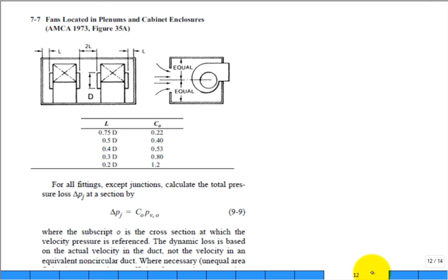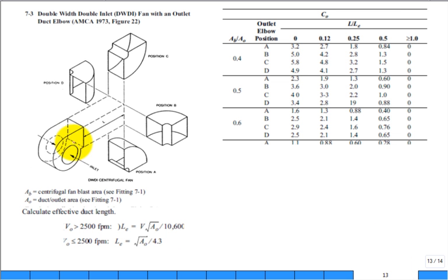You may find that the fan wasn't planned to be installed, or the manufacturer shows you its ratings and curves tested in a really tight room next to another fan. And you can get the system effects to start to be significant amplifiers. Here's one: if you put the outlet to discharge, you might think, oh, I need to turn it this way, right? Or I need to turn it down, or I need to turn it up, or I need to turn it that way.